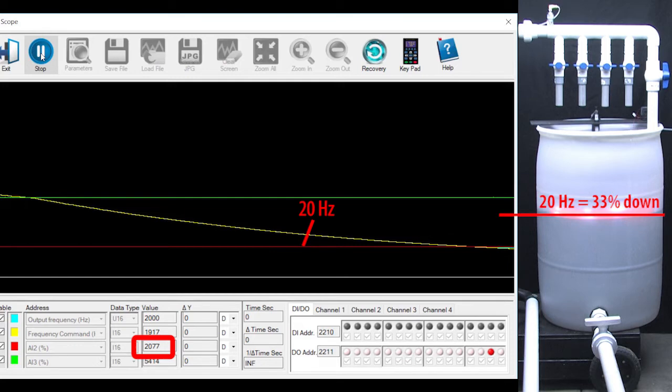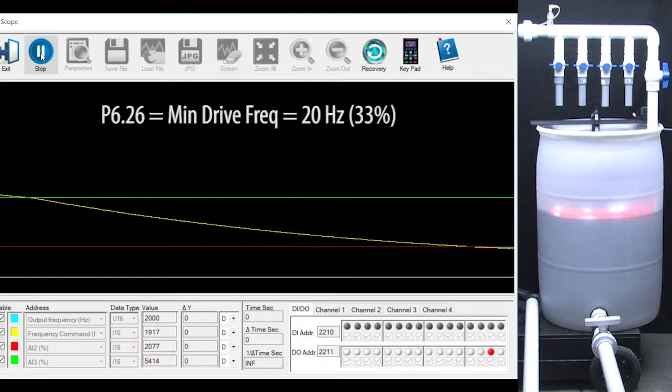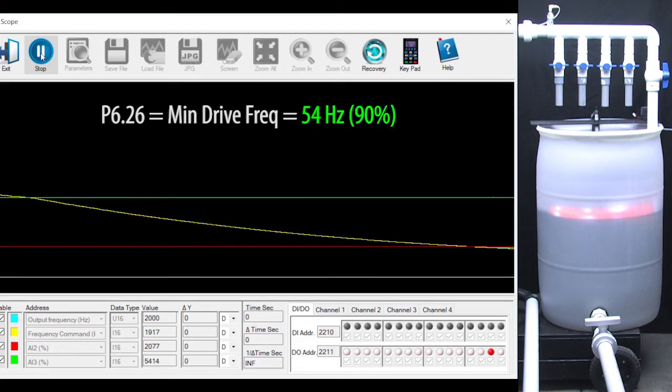The solution is simple. We just raise the minimum drive speed to a larger value and that keeps the motor going fast regardless of the command frequency. I'll set it to 90% of the full 60 Hz, which is 54 Hz.